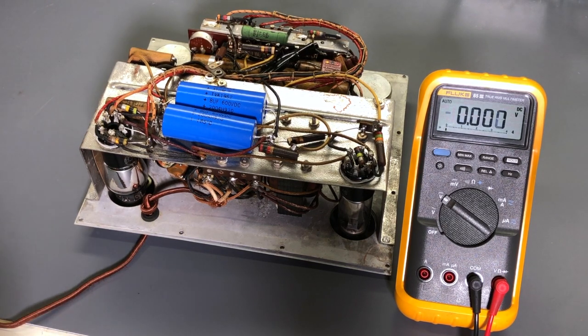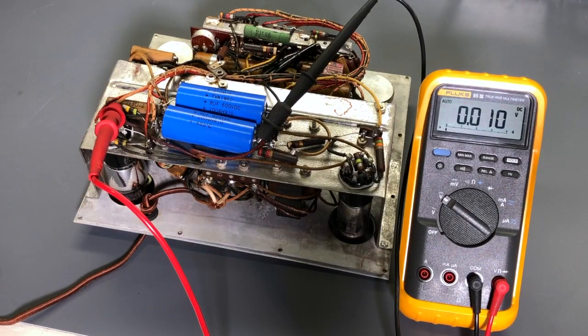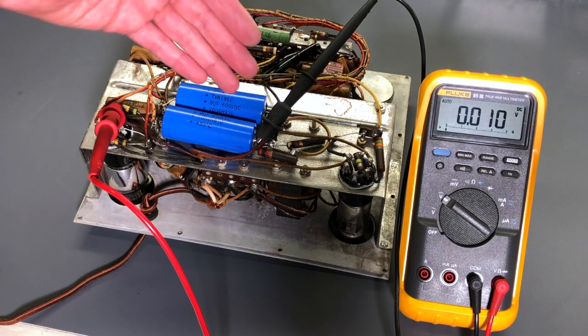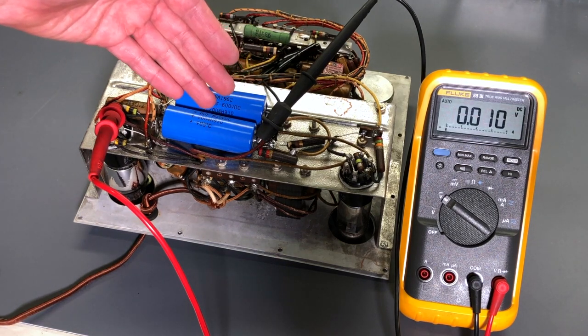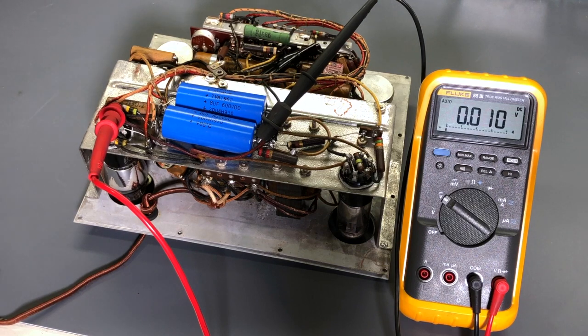I'll get the voltmeter connected here so we can monitor the voltage. Okay, the voltmeter is connected, and it's across the main filter capacitor, so we'll be measuring the voltage as I bring the AC up slowly. And once I bring the voltage up to a low level, I'll let the unit sit for about a half an hour at that low voltage, and watch for any signs of problems or any troubles, and then from there we'll increase the voltage some more. So at this point we'll turn on the isolated supply.